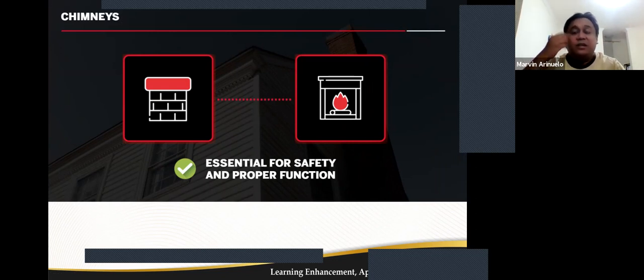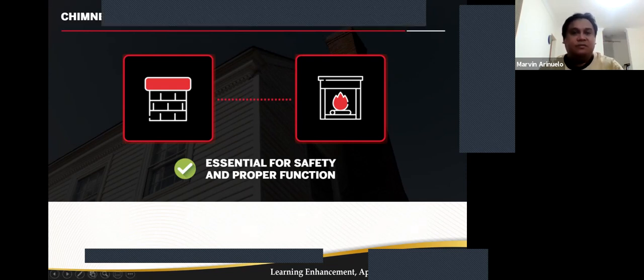The technology of matching the size, height, and configuration of the chimney to the temperature, type, and quantity of fuel, and its correct capacity, is very important for safety and proper function. Those principles are covered in the ASHRAE handbook or ASHRAE standard. Here in Qatar, I think this is not really common. Normally it is in snowing or winter countries, where winter is below 0 degrees.